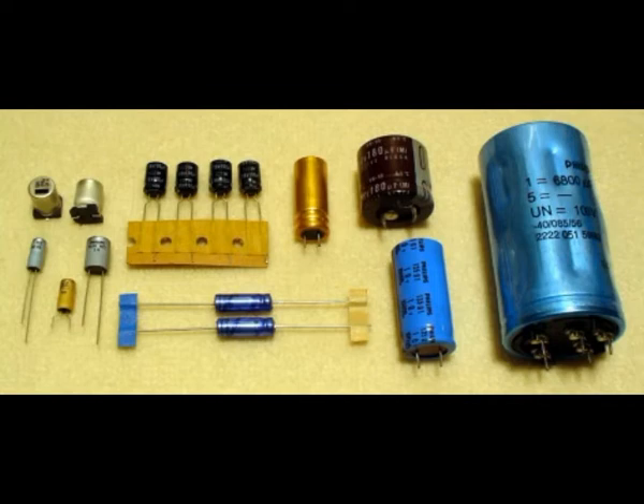Normally the leakage current is always lower the longer the capacitor voltage is applied. The leakage current during operation after, for example, 1 hour is the operational leakage current. This value depends strongly on the manufacturer's series characteristics. It could be lower than 1/100th of the specified value.